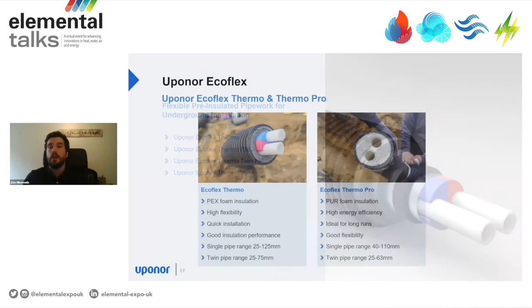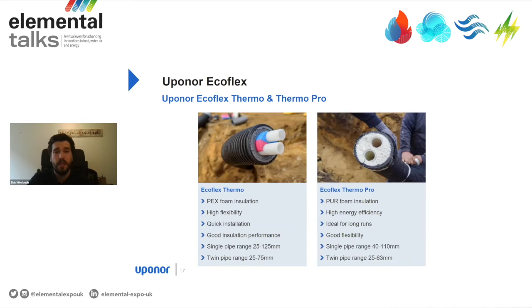So Ecoflex Thermo and Thermo Pro might look similar on the outside, but they have some big differences on the inside. The service pipe for both ranges is actually PEX pipe, but the Thermo range comes with PEX foam insulation, which achieves a very good insulation performance, and also enables the pipe to be highly flexible, which makes it ideal for the final branches before the pipe enters the building. The Thermo Pro comes with PUR foam insulation, which provides low U values, which means lower heat losses, and leads to higher energy efficiency. The Thermo Pro is actually ideal for long runs and provides good flexibility too.